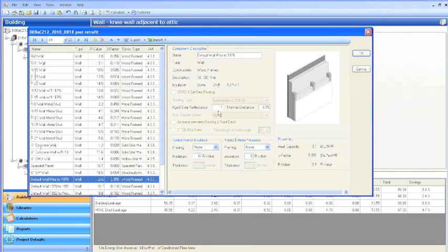So again, if you set up your knee wall, then within the library, the solar reflectance is 1. That means it's a perfect reflector of sunlight, meaning that no heat from the sun can get through that wall. That may seem a little strange because you're talking about the garage. Of course, there's no sunlight at all to bounce off, but the model treats it the same way as if it were completely shaded. Energy Pro doesn't really have a way to say it's adjacent to a garage. We just say it acts like no sunlight can pass through it, no heat from the sun can pass through it.